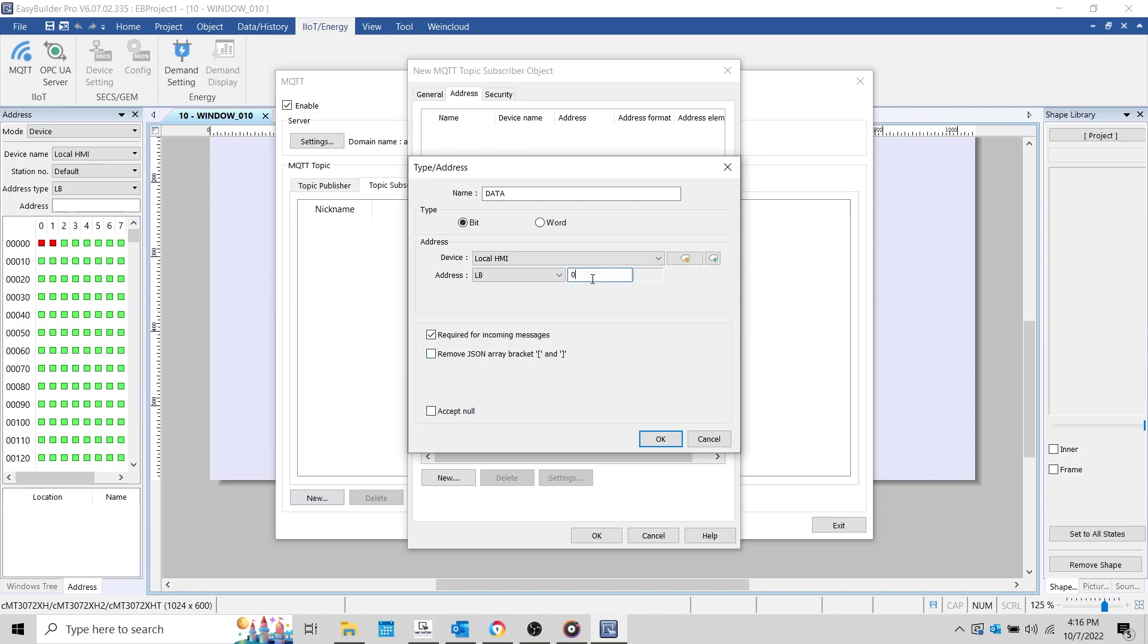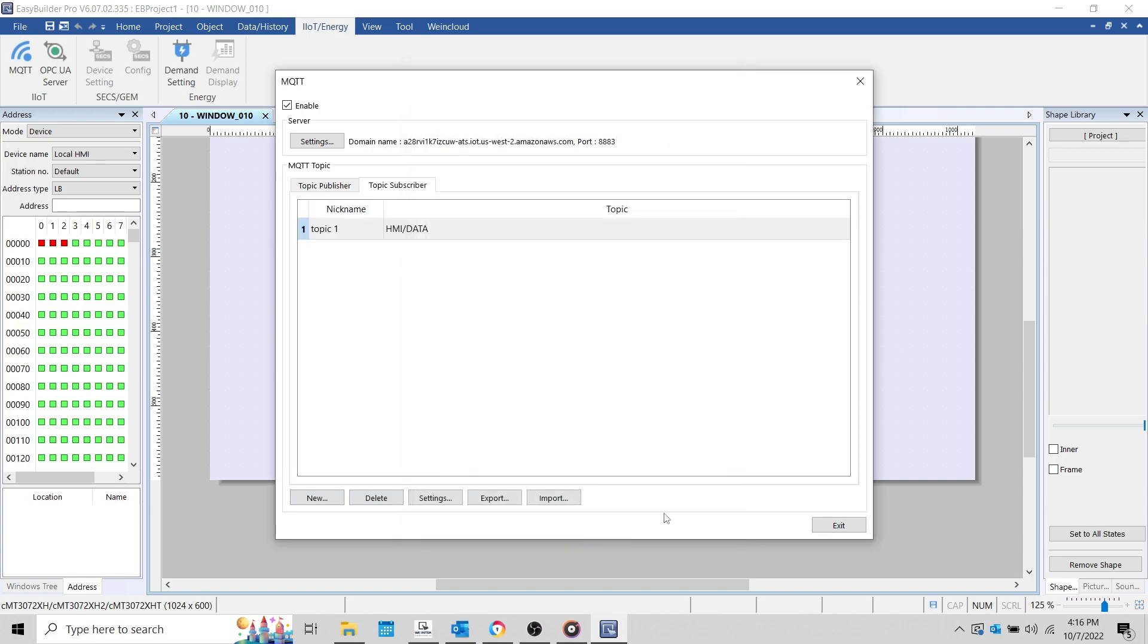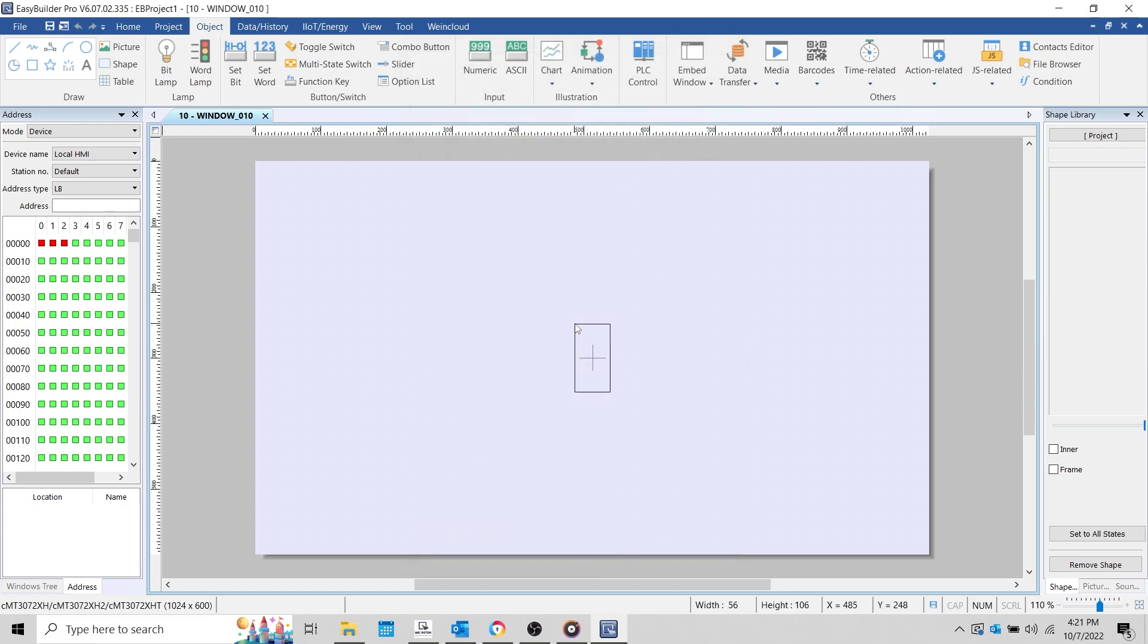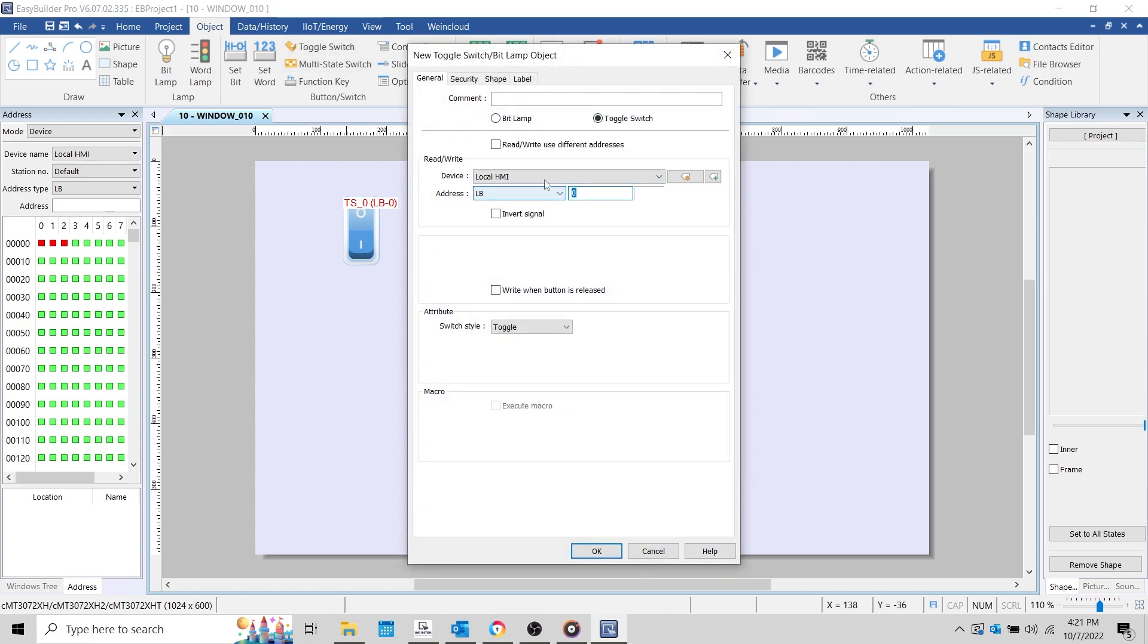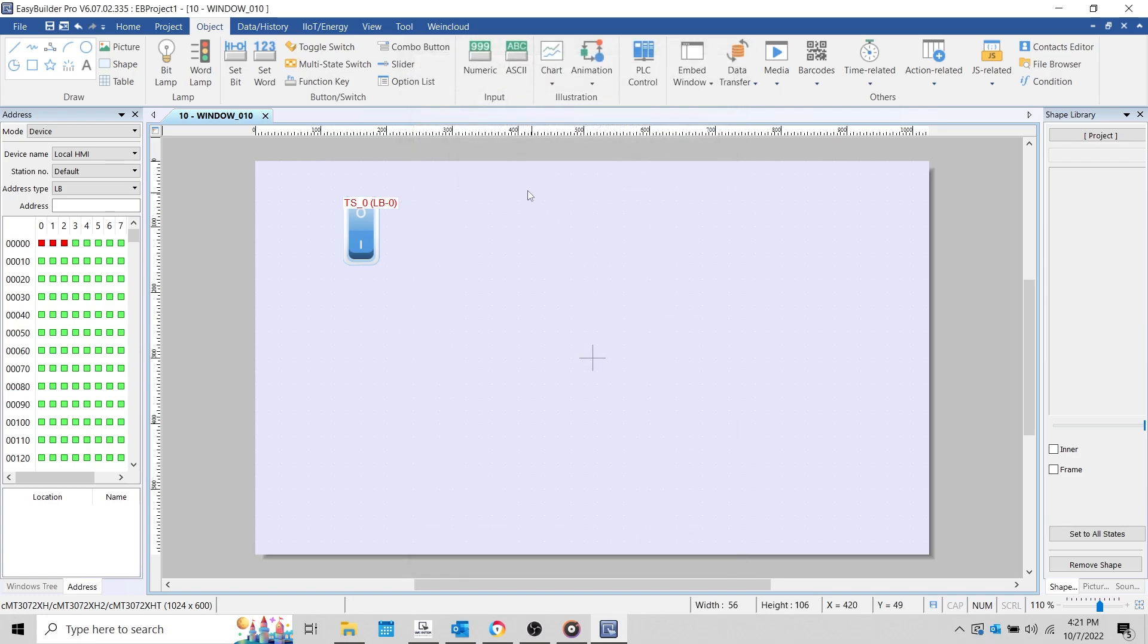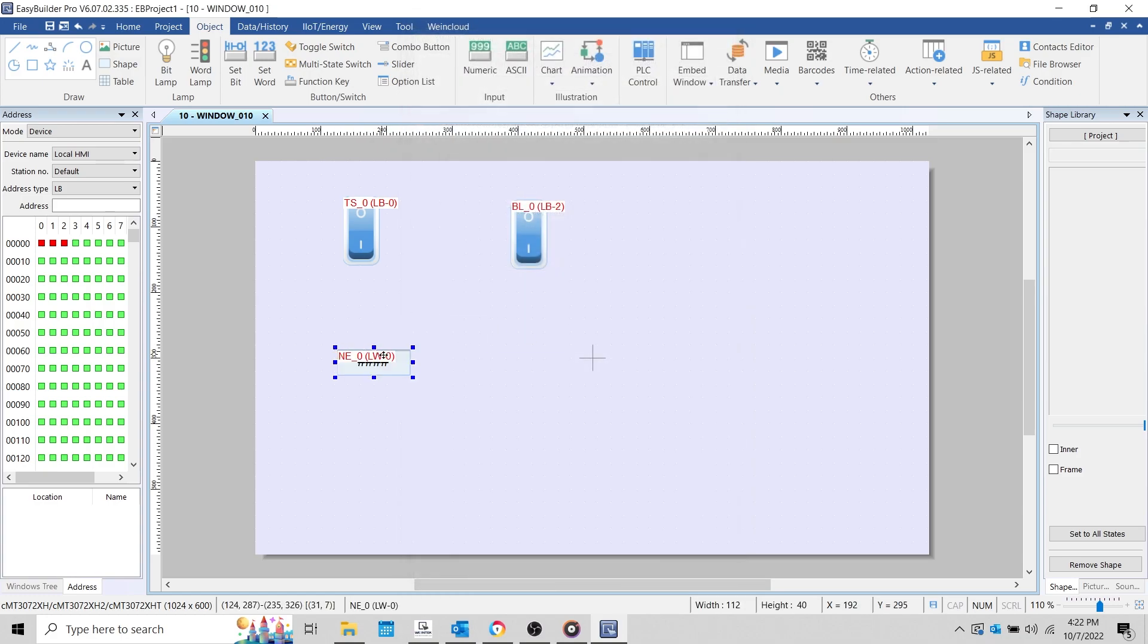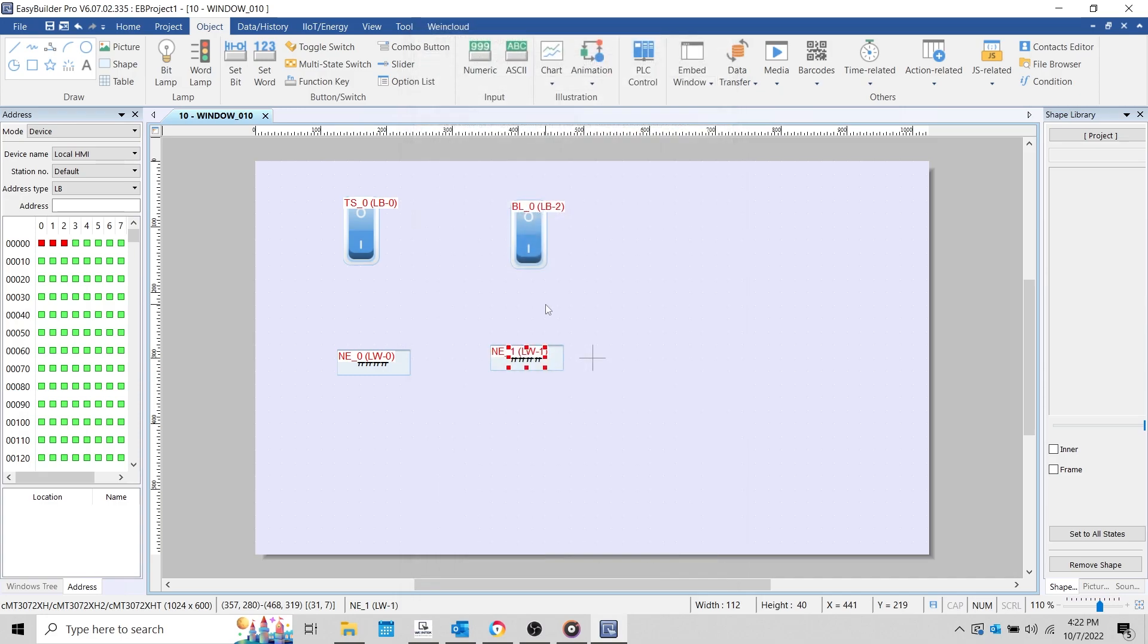With that finished, I'll create some objects that correspond to the addresses defined within our topics, as well as the status and error address used by the MQTT object. To begin, I'll create a toggle switch addressed to LB0. This address corresponds with the data value within the HMI/data topic that the HMI will publish. And since we're subscribing to the topic as well, let's create a bit lamp addressed to LB2. This address is used within the HMI/data topic subscription. Let's create a numeric object for the MQTT status. This should be addressed to LW0. And I'll create a numeric object for the MQTT error register at LW1 as well.